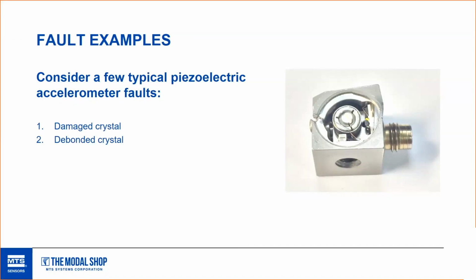Debonding of the crystal, for an accelerometer, describes when the piezoelectric element and the substrate degrade over time. This can affect scaling and frequency changes, again, often seen at higher levels than might be tested with the handheld. And I do want to note, with things like this, you kind of have to trust your vendor. It's the history and pedigree and know-how of the vendor that can give you some reassurance that some of these faults will or won't occur, based on how long they've been doing something and their standing in the industry, really.